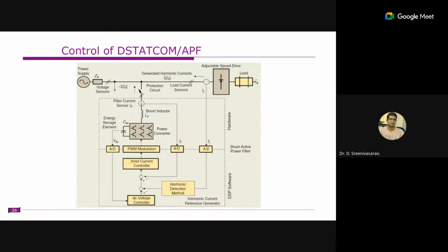Now, the control of this D-STATCOM. Another thing is that D-STATCOM and active power filter, both terminologies can be used interchangeably. The control objectives are the same. Sometimes we call it a D-STATCOM, or sometimes we call it an active power filter, but both are the same.